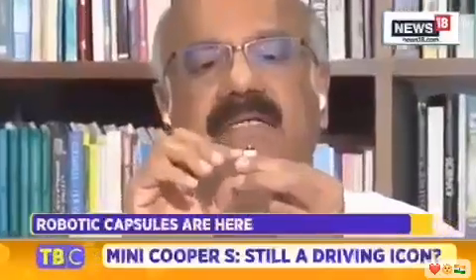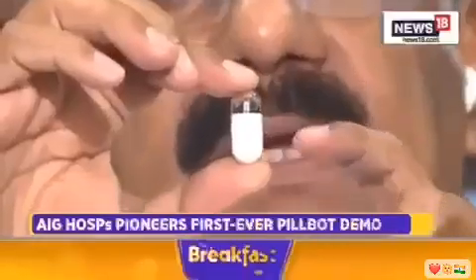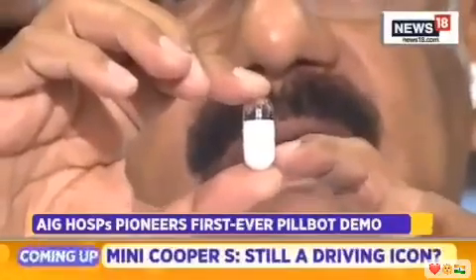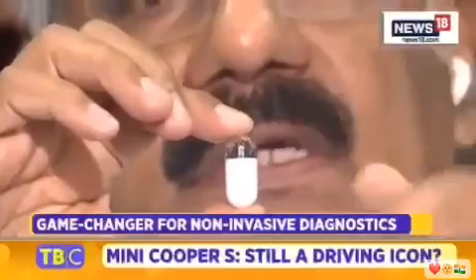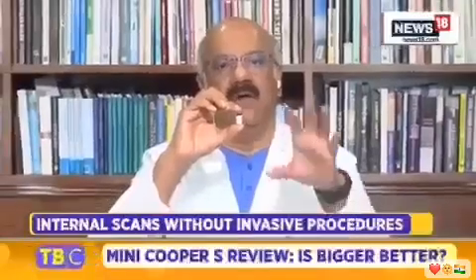This is very interesting technology. This pill is very small, just like an antibiotic. You can see the LED lights and the camera on top. You swallow this pill, it goes inside the body, and then the camera gets activated. There are batteries and a transmitter packed into it. It transmits images by radio frequency to a television screen outside, or you can use a belt which receives all these images. Once inside, it produces a continuous video — approximately 60,000 frames throughout the gastrointestinal tract.